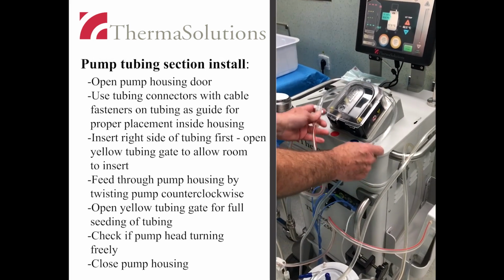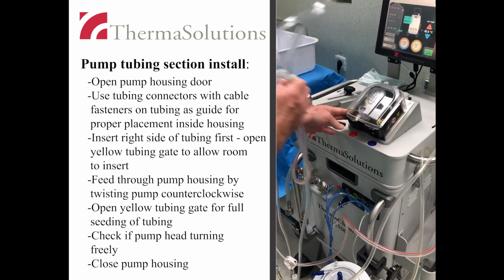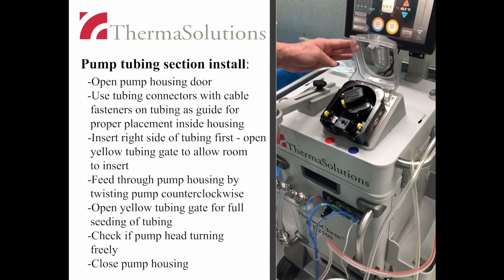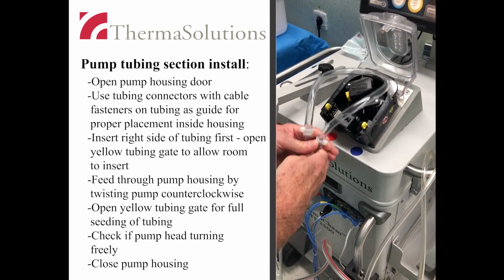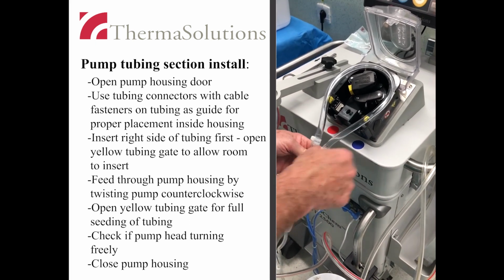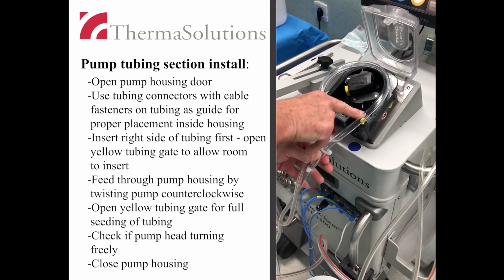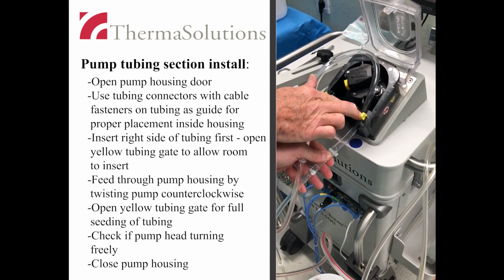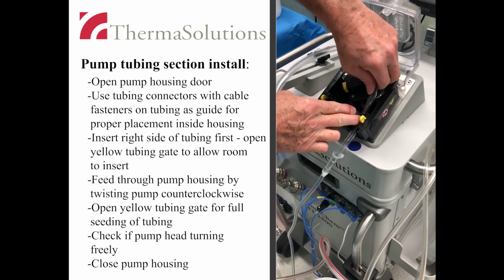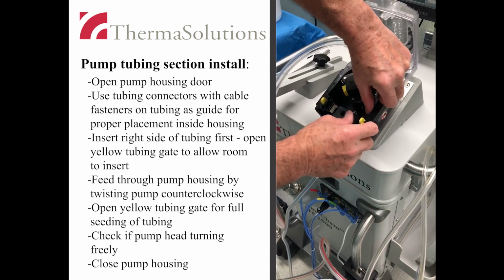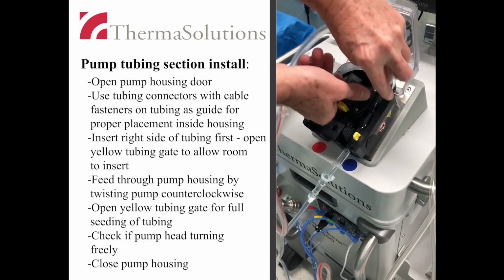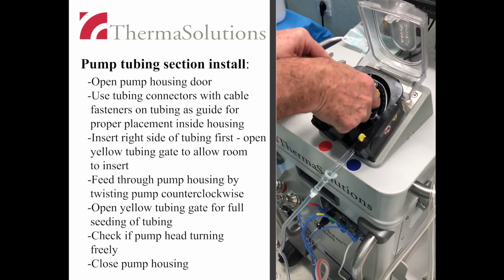Insert the pump tubing section into the pump housing using the following steps. Open the pump housing door. Use the tubing connectors with cable fasteners as a guide for proper placement of the tubing within the pump raceway. The connectors and cable fasteners should both be outside the pump housing. Use the colors on the tubing to match the colored dots outside the pump housing as a guide.